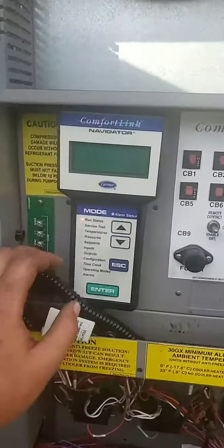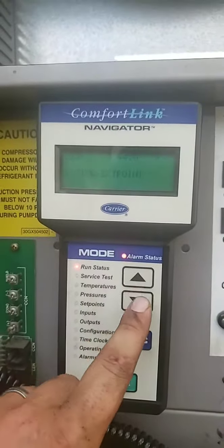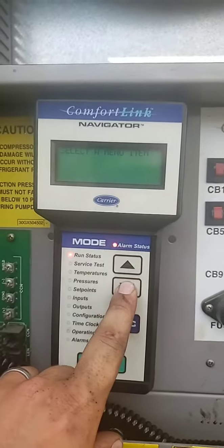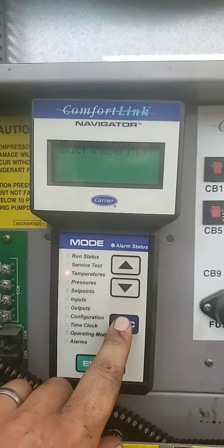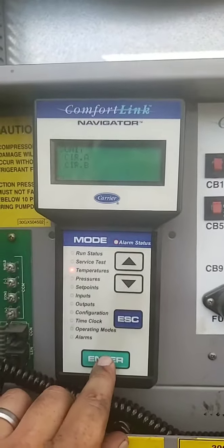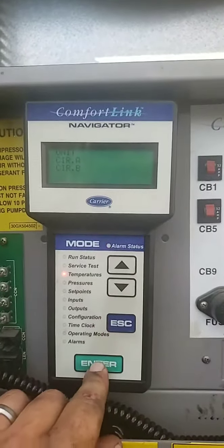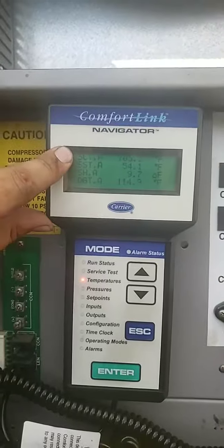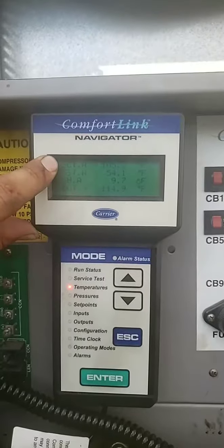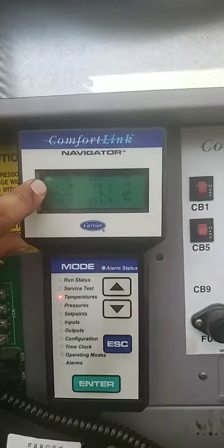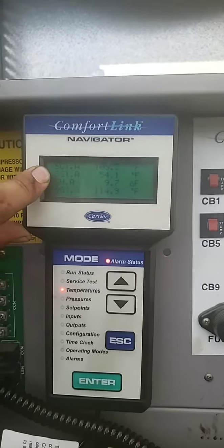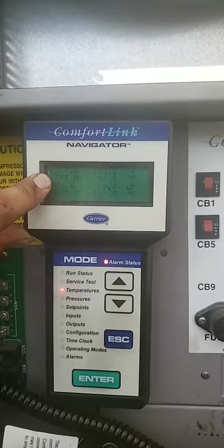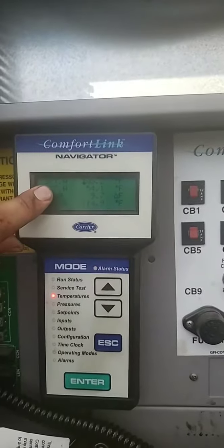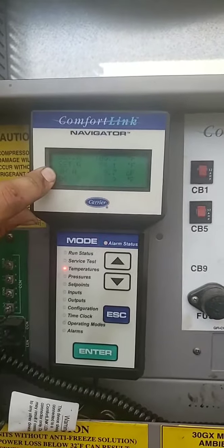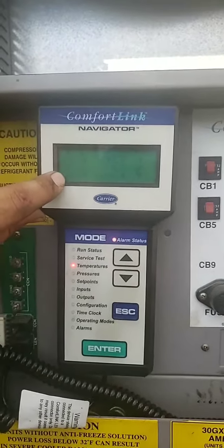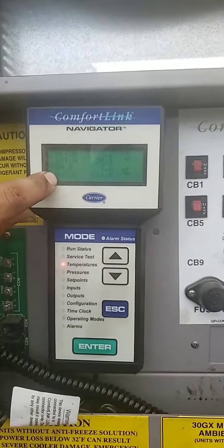Coming over here to the controller, let's see if we can get this to pull up. Can y'all see that? Yeah, kind of, sort of. All right. So we're going to come down here to temperatures. So you can see unit, circuit A, circuit B. Let's look at circuit A. This SCTA, that is saturated condenser temp. You see it's 105 saturation. That's just standing pressure. The system is not running. The SST, that is saturated suction temp. That dot A is circuit A. The SH, that is our superheat on the system. And then DGT, that is your discharge gas temp.